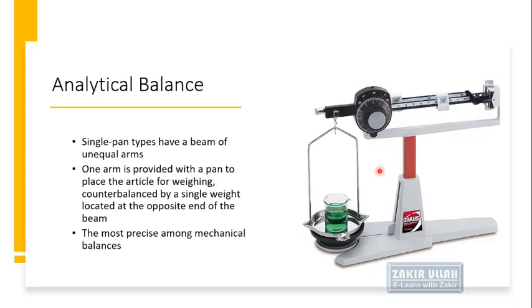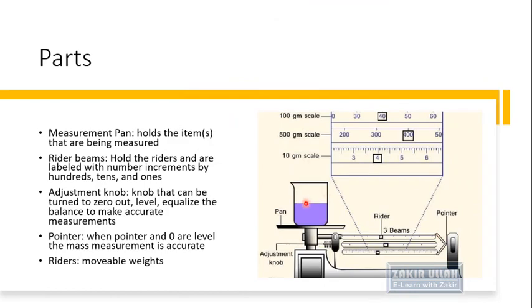Another type of analytical balance is the single pan balance. It has a beam of unequal arms — one arm supports a pan for placing the article, and it is balanced by a single weight at the opposite end of the beam. This is one of the most precise mechanical balances used in the laboratory. Its parts include the measurement pan, rider beams, adjustment knob, and pointer. The measurement pan holds the item to be weighed, and the rider beams show the tens, hundreds, and units of the weight.